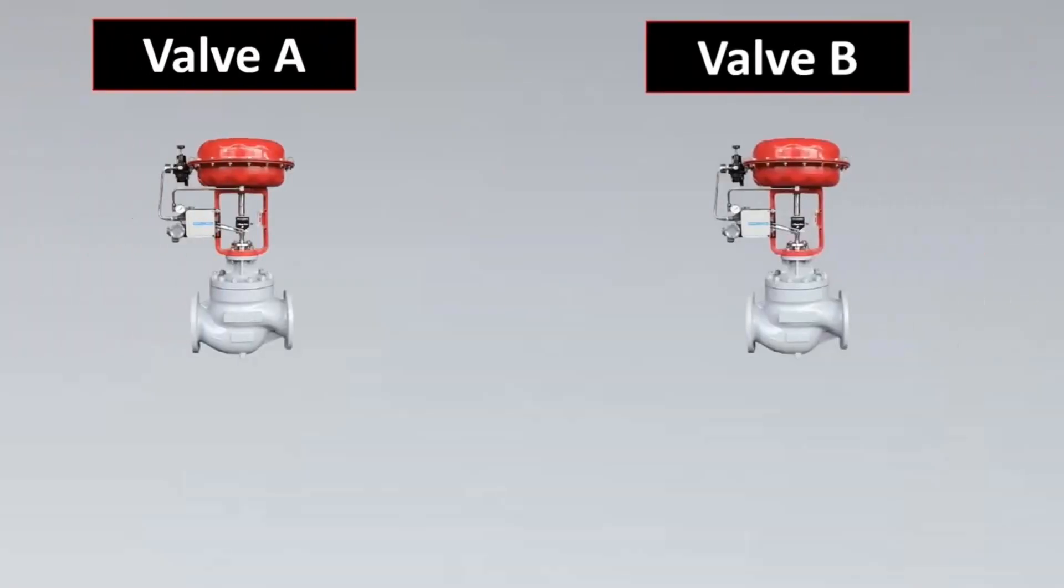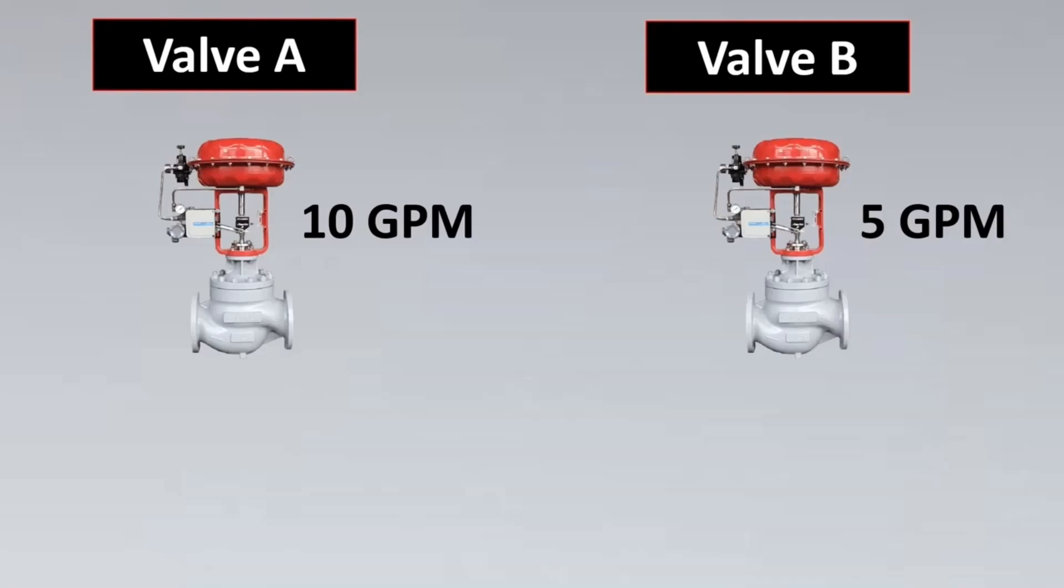Valve A has 10 GPM and valve B has 5 GPM. We cannot say that valve A has higher flow capacity because there could be the case that both valves are made of the exact same construction and size, but the pressure drop across the first valve is 15 psi while the second valve is just 1 psi.